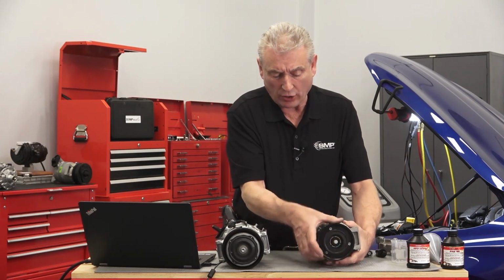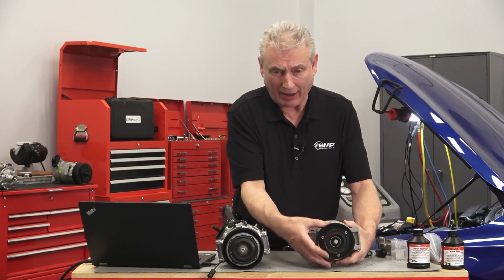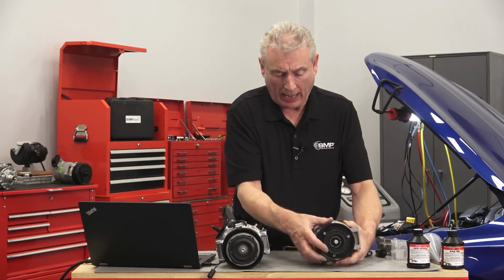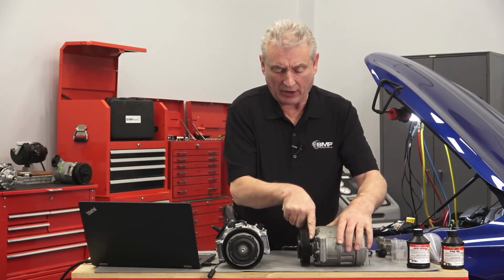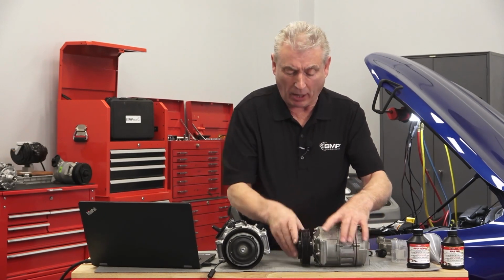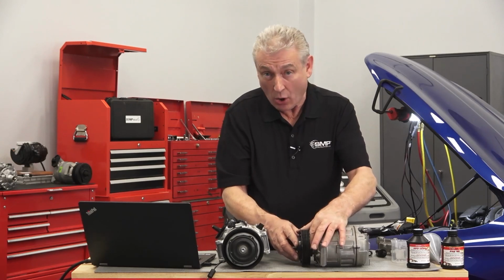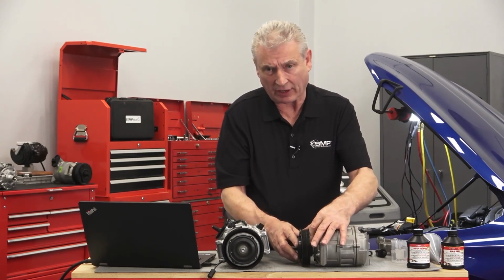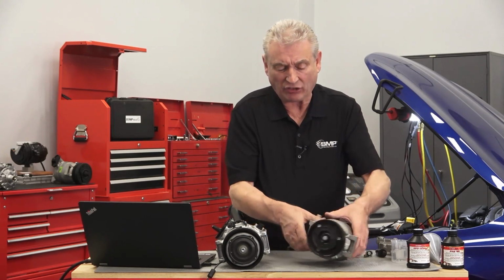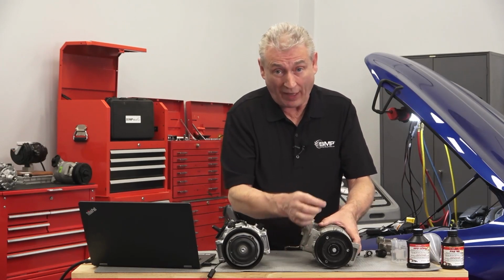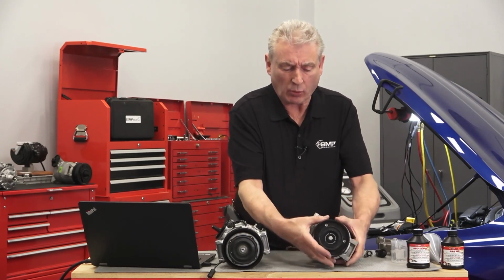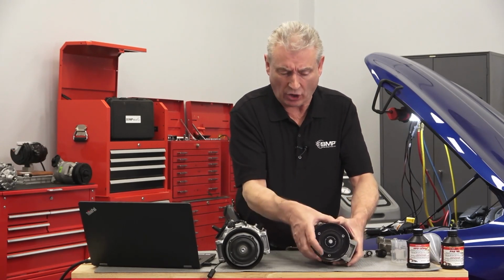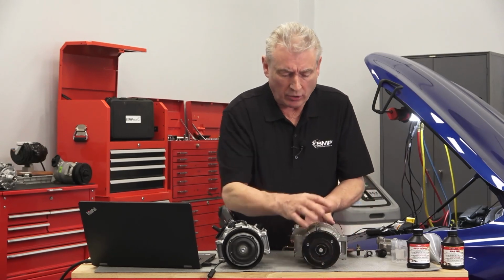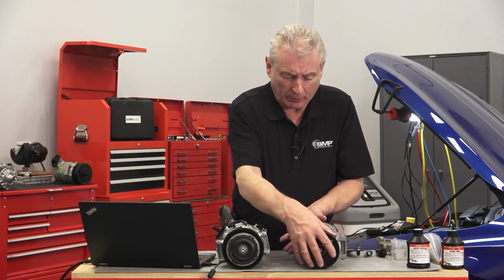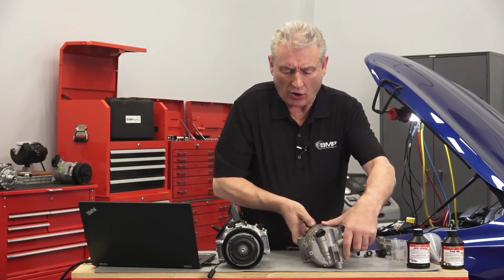When I turn the pulley, the crankshaft of the compressor is turning all the time. If we look behind the pulley, you can see there's actually no clutch, no electrical clutch on this compressor. This means that even when it's 40 below and the air conditioning is off, the crankshaft of the compressor is still turning. Now, to control the output of these compressors, there is a solenoid in the rear head.